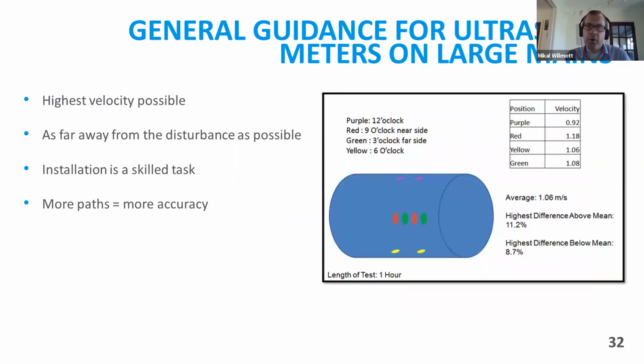If we move on, we did an experiment in Severn Trent on a large main, a 600mm main. We had an asymmetrical flow profile, I believe, in the main, or maybe even some swirl in the main. We put on 4 ultrasonics, and we got 4 different answers. 2 were quite close to the average, and then 2 were quite different. And so for me, this was an example of how, on larger mains, especially if they're strategic mains, you would want to put on quite a number of paths to increase that confidence. And we put these on 100 diameters or more from the last disturbance. Andy, if you'd like to.